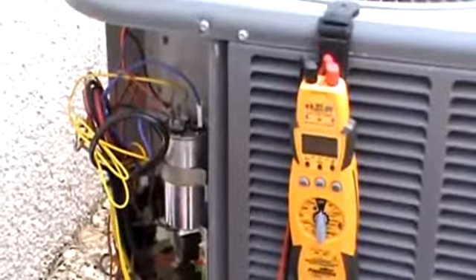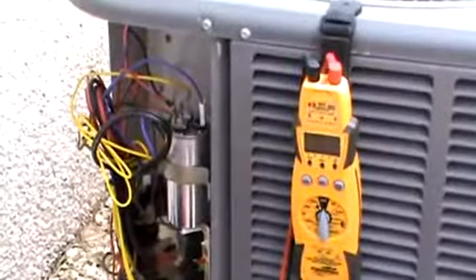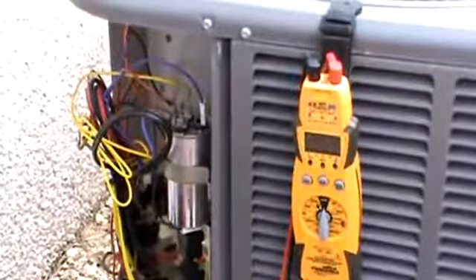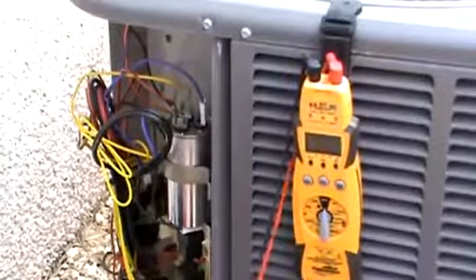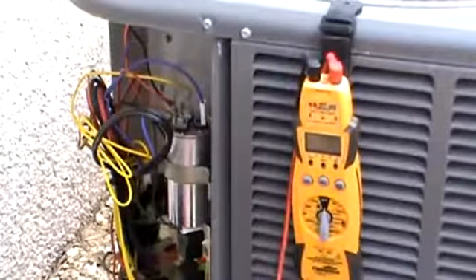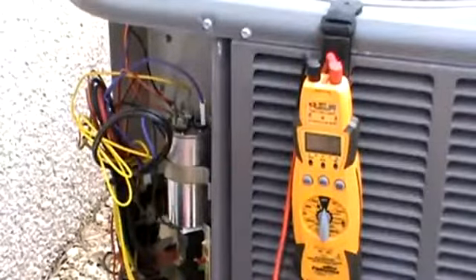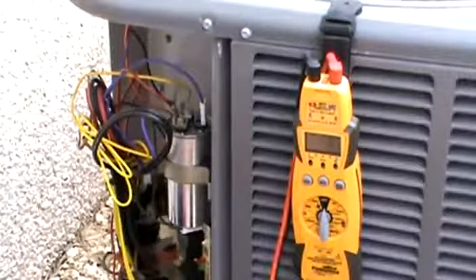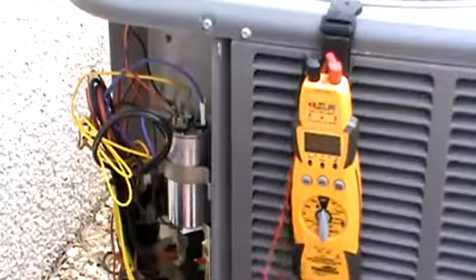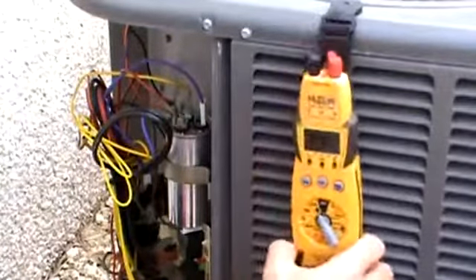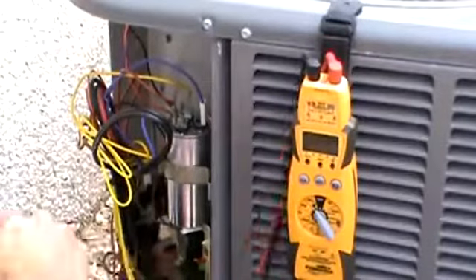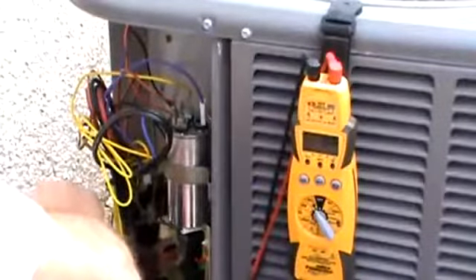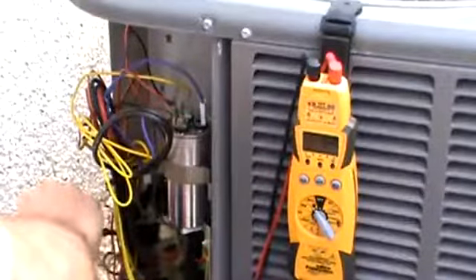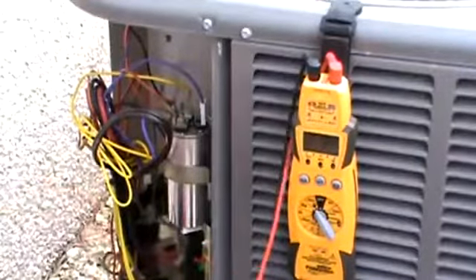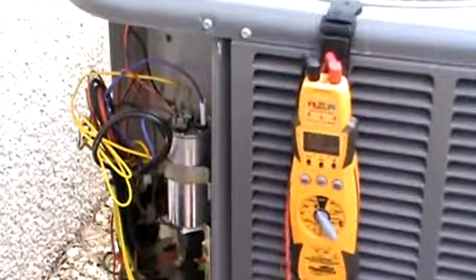The second part about being safe when checking out your capacitor is to ensure that the power is in fact de-energized to the unit. I've had systems where another technician hot-wired the disconnect box, and even though it was pulled out, there was still power to the unit. So you take your voltmeter, put it on your volts AC, check the incoming power. There's no power coming in, so we now know it's safe to remove our capacitor to check it out.